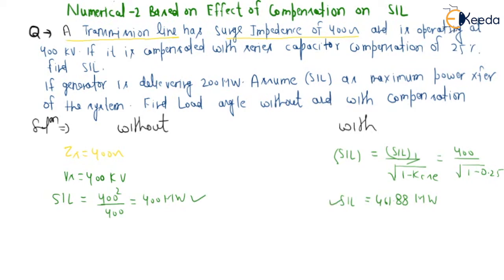Now for the power transfer of 200 megawatt: P equals Pmax sine delta. So 200 megawatt equals 400 megawatt sine delta. From this, delta will be equal to 30 degrees without compensation.